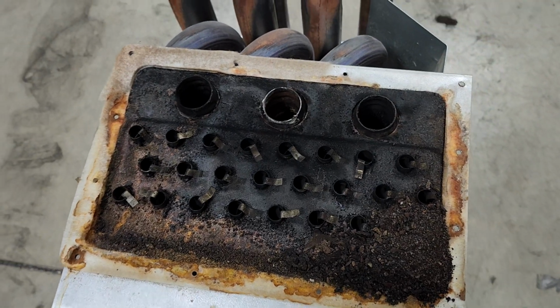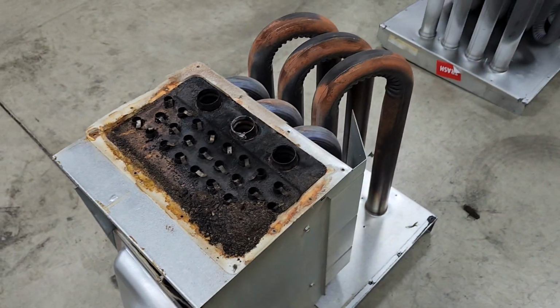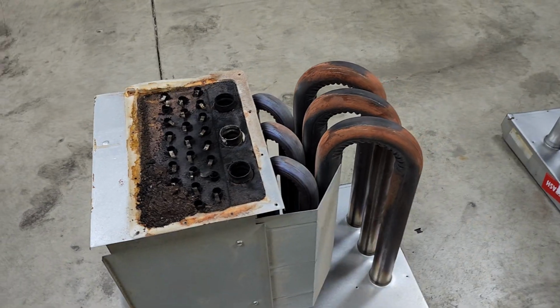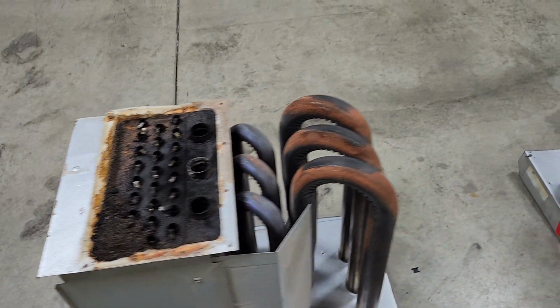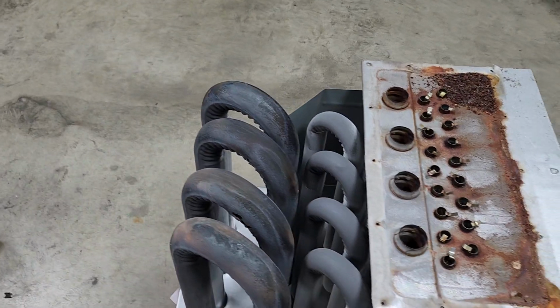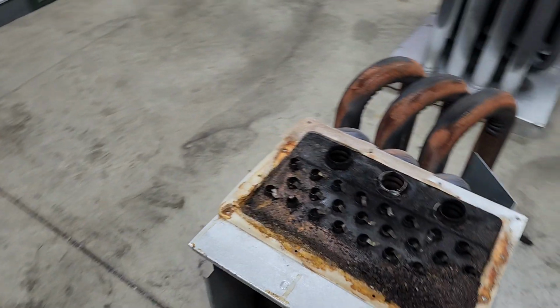Again, all of this could be prevented if the technician sets the gas pressure during commissioning and verifies airflow, static pressure, and CFM. It is also the responsibility of the homeowner to have annual maintenance done, replace air filters on time, and keep the duct systems clean.